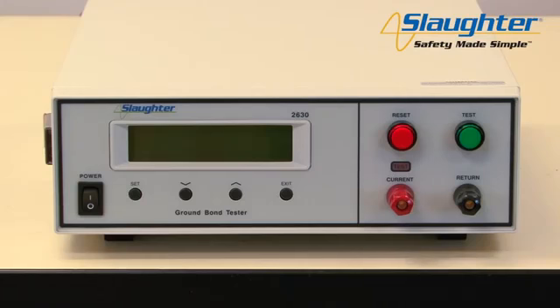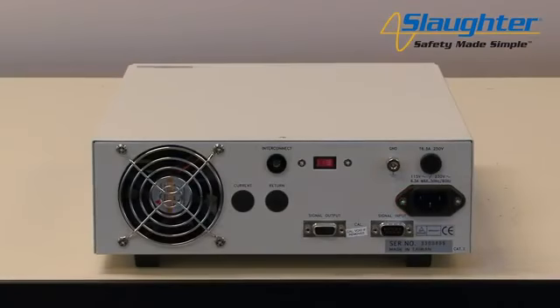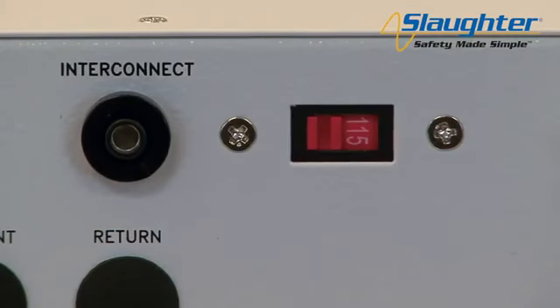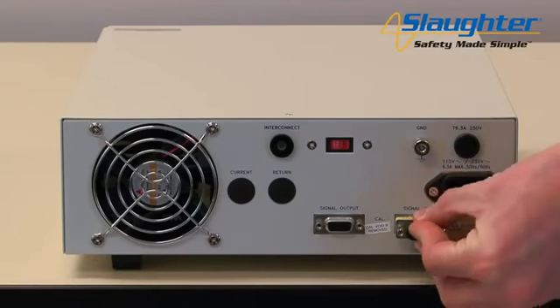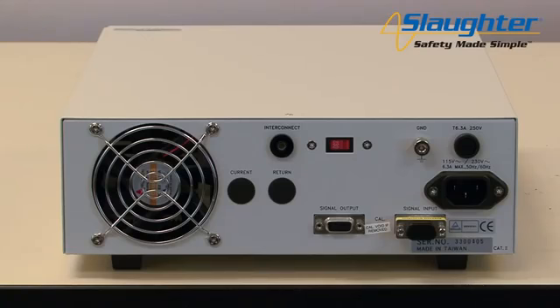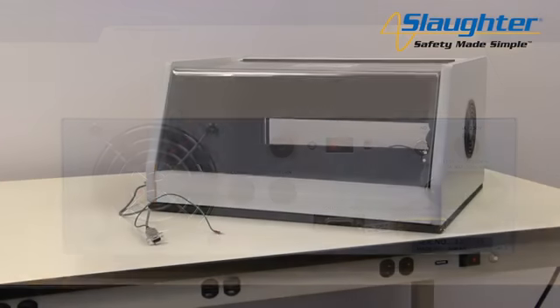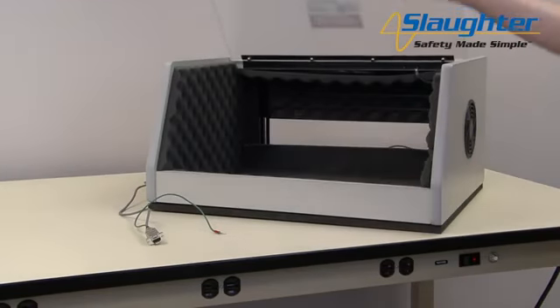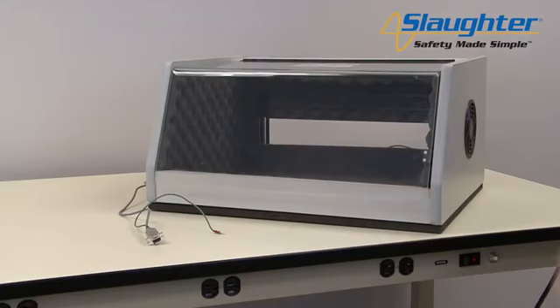First, you'll need to power up your 2630 tester. Check to be sure the correct input line voltage has been selected on the rear panel, either 115 volts AC or 230 volts AC. You'll also need to insert the remote interlock key into the 9-pin signal input terminal on the rear panel of the 2630. The tester will not output voltage unless this interlock key is properly plugged into the signal input. This allows the user to wire pins 4 and 5 up to the doors of a DUT enclosure for an extra measure of operator safety. A DUT enclosure provides a means of positive protection for the test operator.